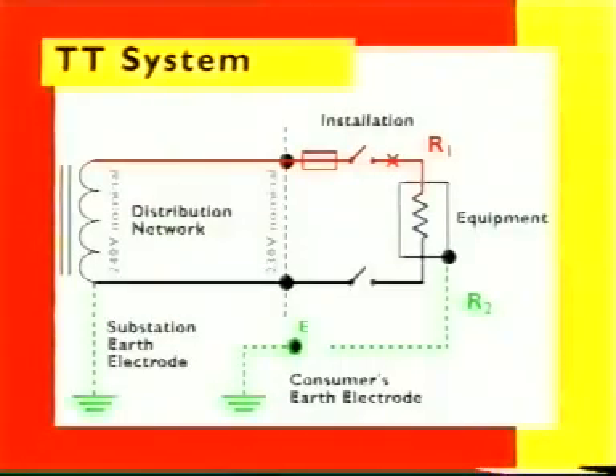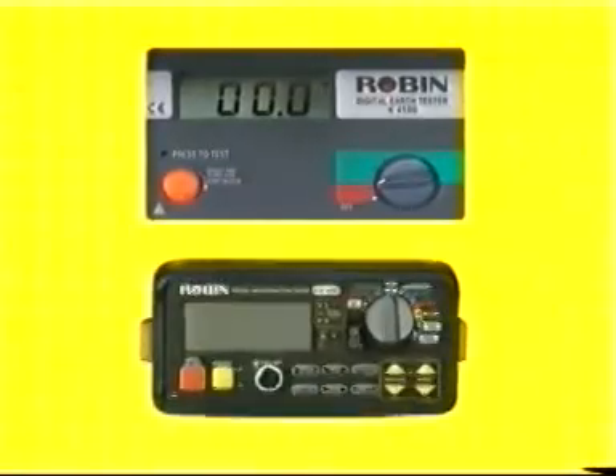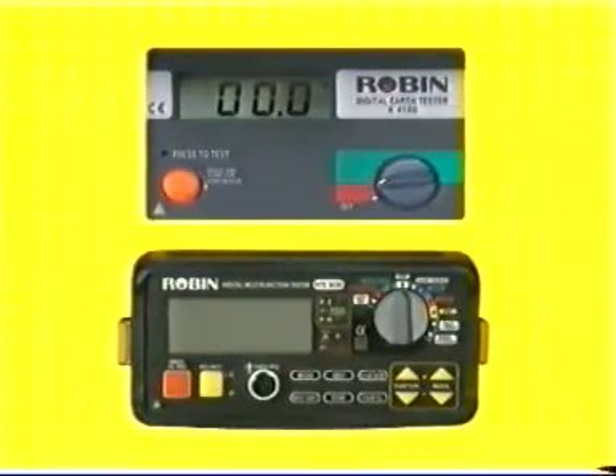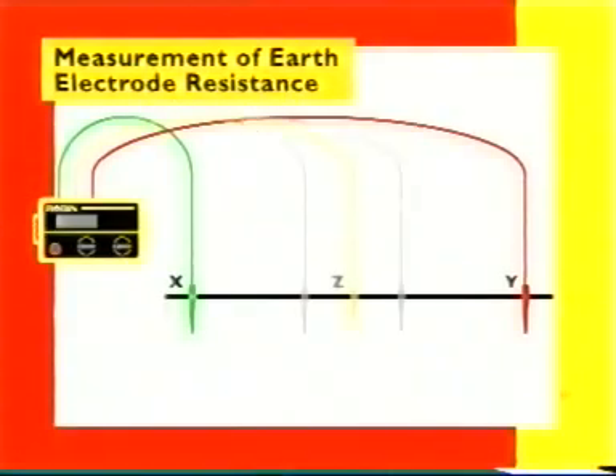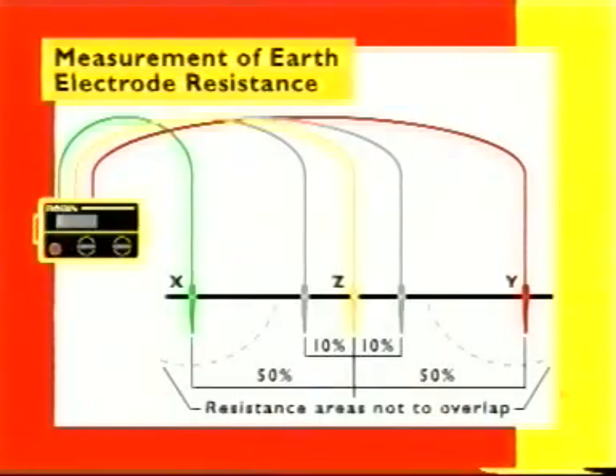TT systems are reliant upon a sound connection with the mass of earth for protecting installation users against indirect contact shock. Electrical tests must confirm an effective earthing system to prevent hazardous shock voltages appearing on exposed metalwork. The resistance of the consumer's earth electrode relative to ground should be in accordance with recommendations in the current edition of the Code of Practice for Earthing.